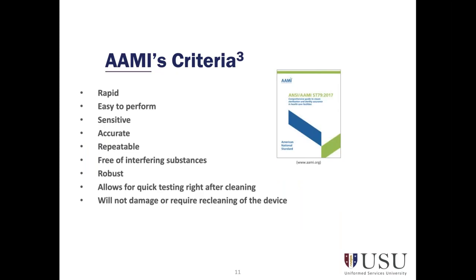As previously mentioned, several test methods are commercially available for the rapid detection of organic residues left from surgical instruments. Ideally, and according to AAMI's, a point of use verification system should have these 9 elements. It should be rapid. This means that the system can provide just-in-time results so the end user can make just-in-time decisions. It should be easy to perform or simple to use.